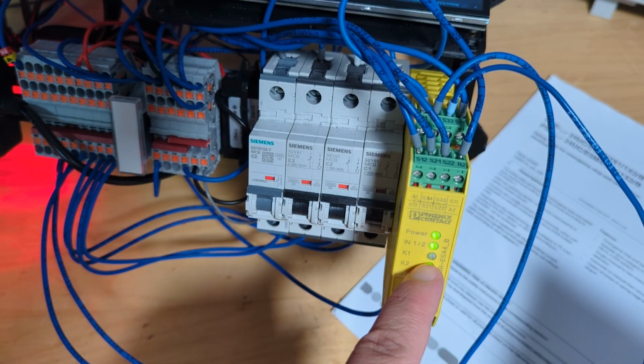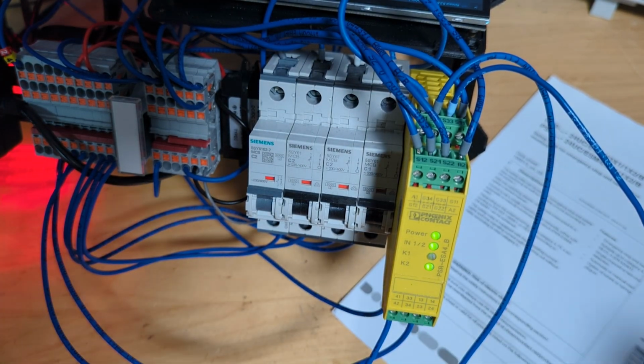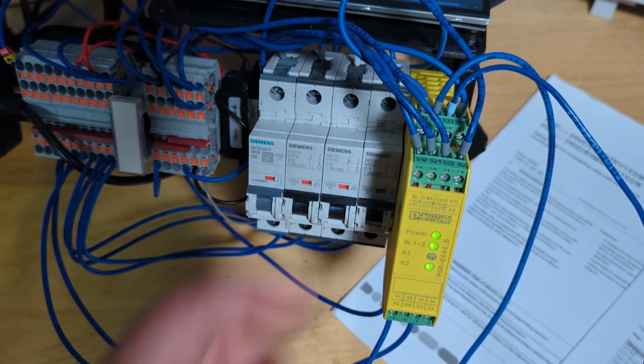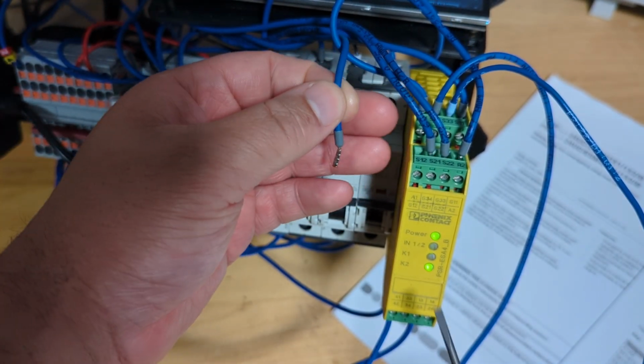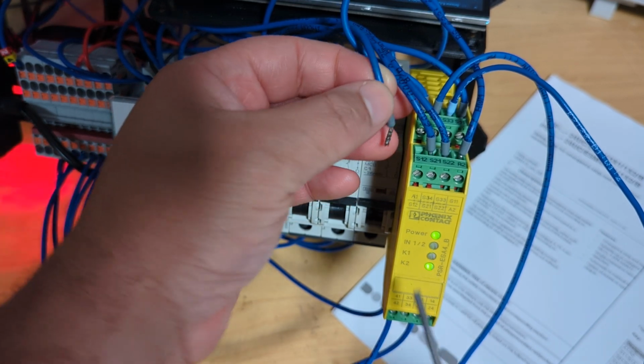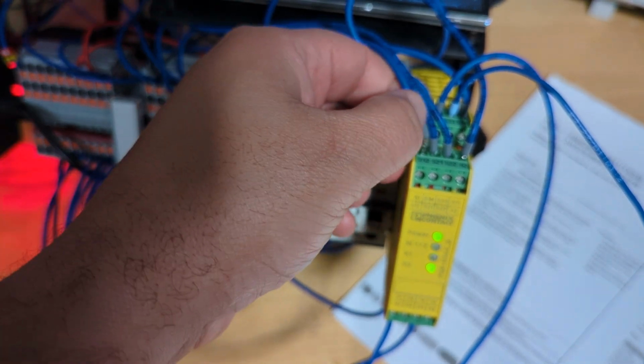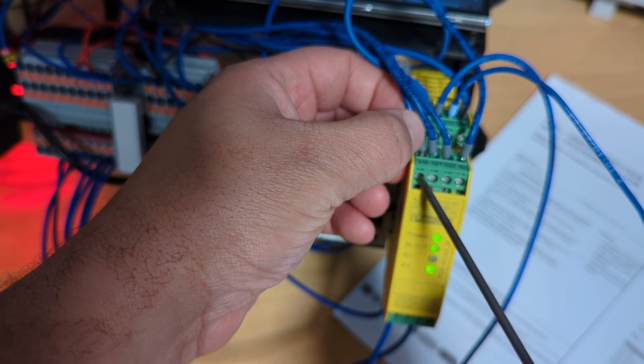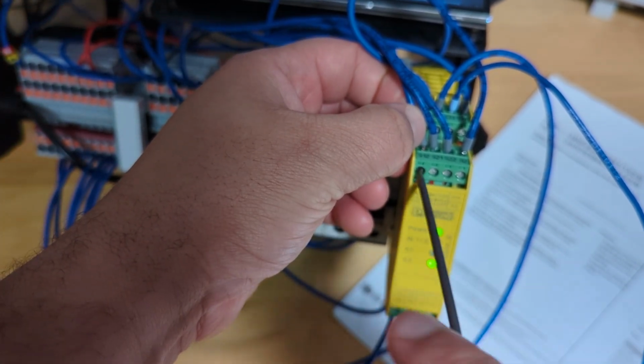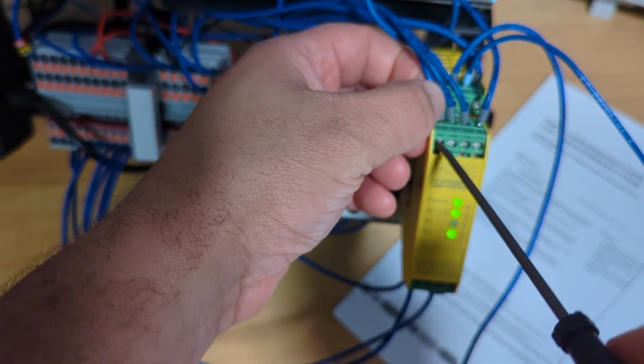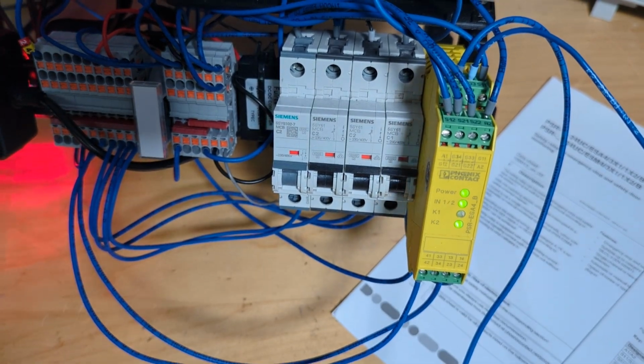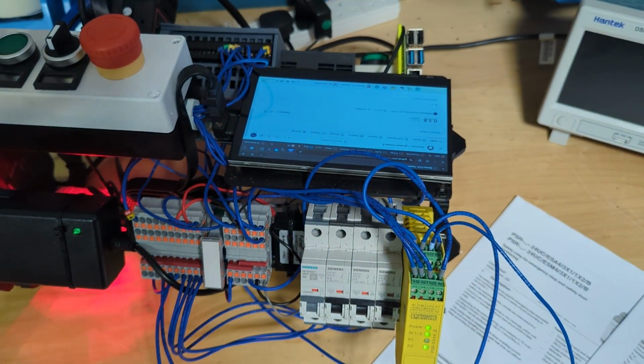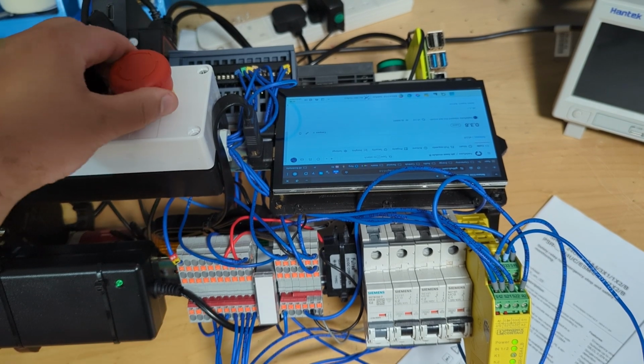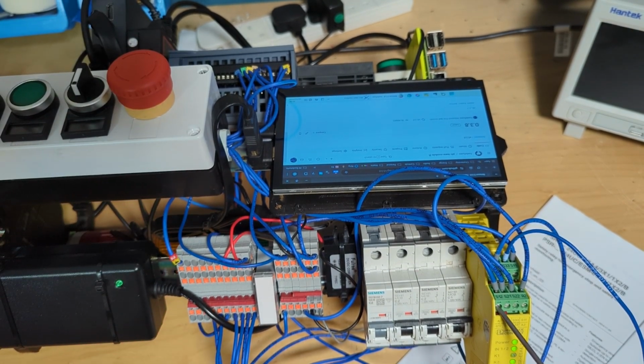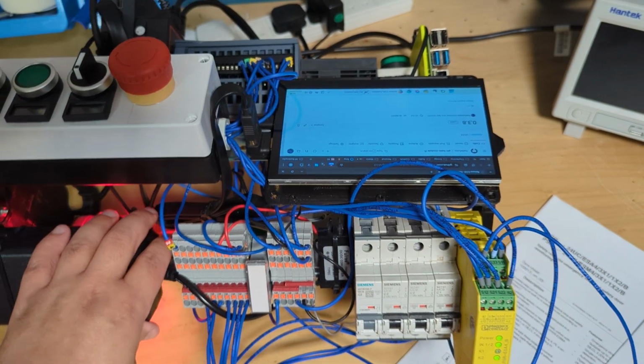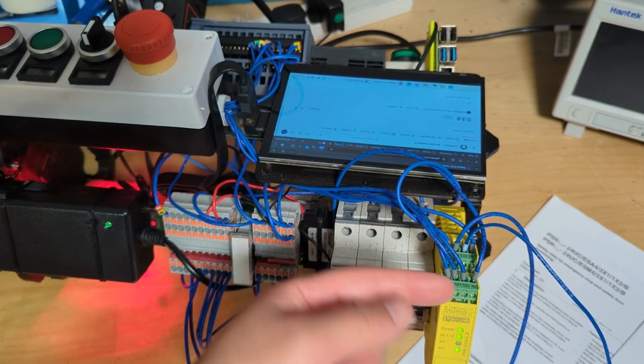Right now, K1 is not happy. All these have opened because I lost that channel. Now if I take it out completely, I lose that LED as well. If I put that back in, it's going, okay, I can see the e-stop again, but I'm still not going to be happy with you. Right now, my e-stop isn't pressed. That's the important thing to know, and that's the great thing about these devices. My e-stop's not pressed right now, but the safety relay detected a fault on the e-stop circuit. If that wire had broken, it would have done the exact same thing.